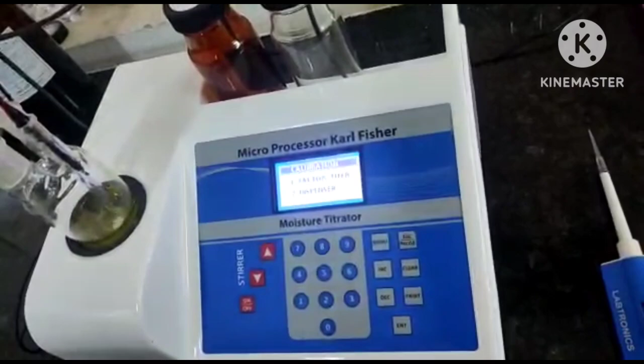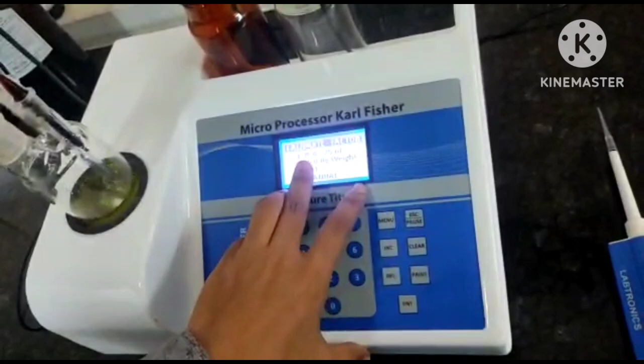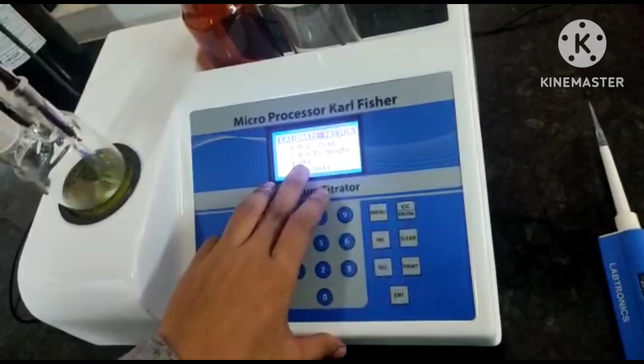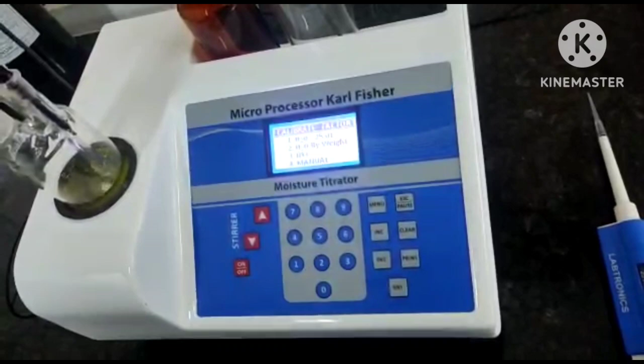You can calibrate it after 3 months or 6 months, but there is no regular calibration needed for dispenser calibration. So first we have to go for the factor calibration. In this we have 4 options. First, H2O by taking 25 microliter of water; second, H2O by weight; and the third one is the DST option, the disodium tartrate option. So these are the 3 types of calibration we can do.